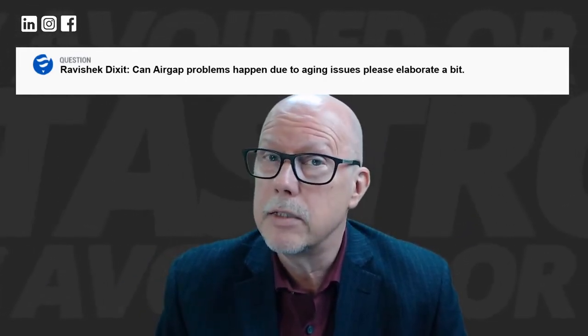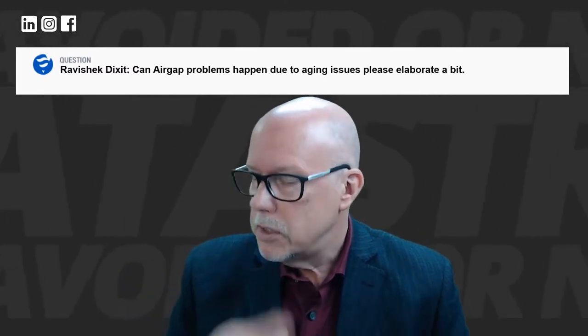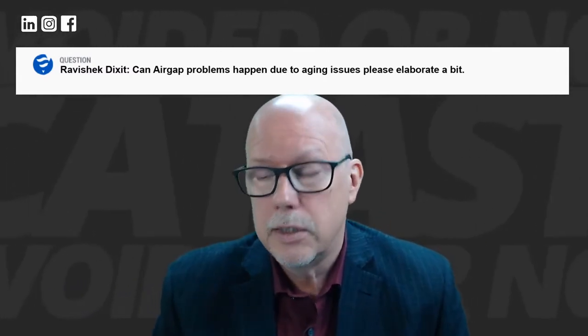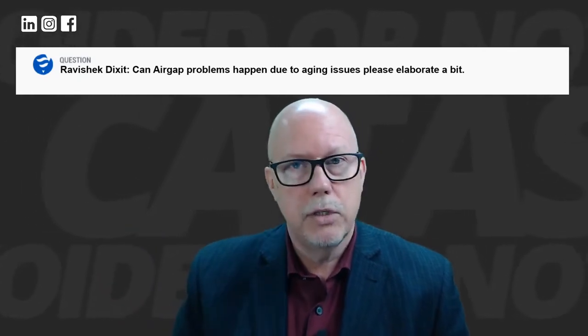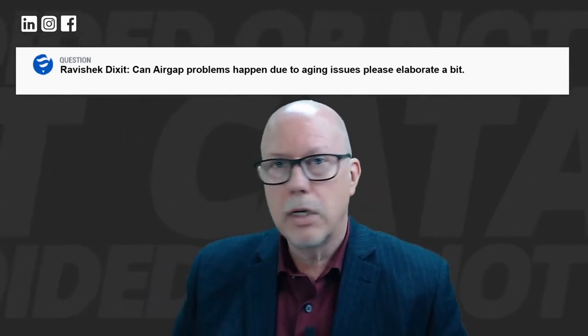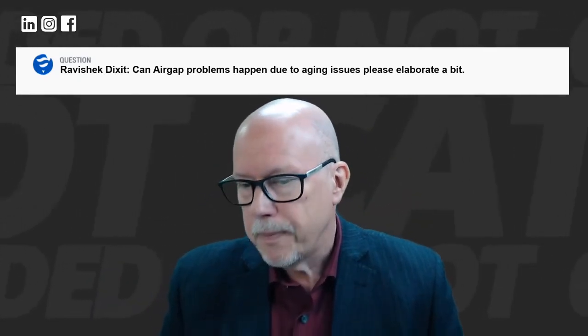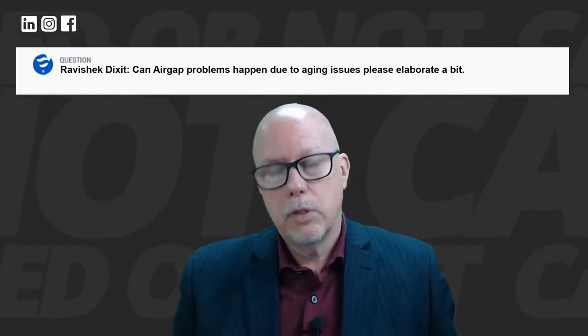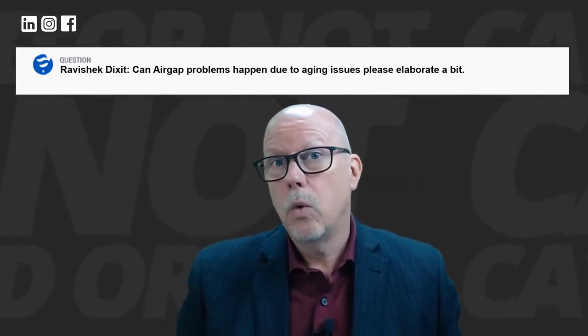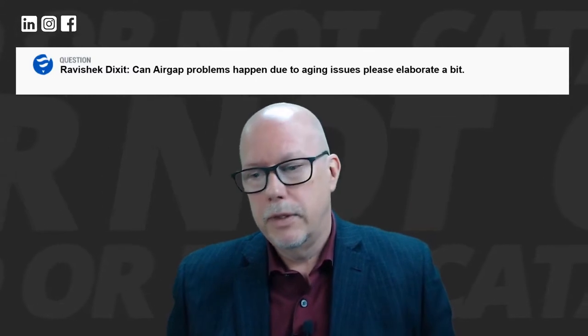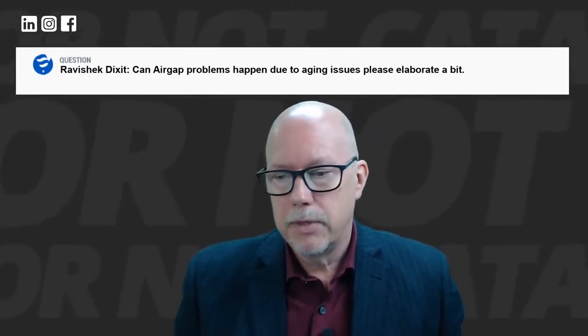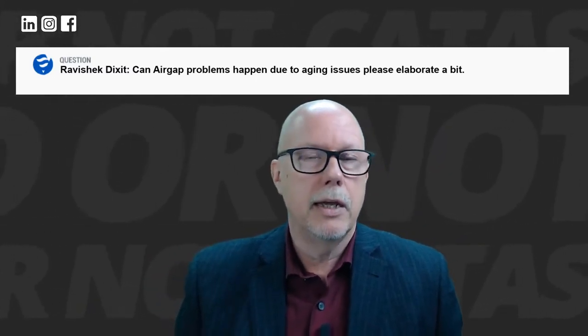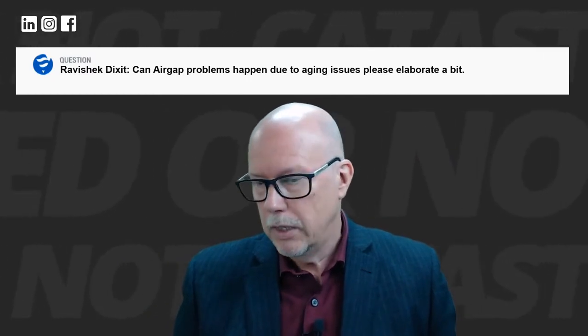So our guess was that they could run this unit safely, since it had been running like this for 20 years. The utility put the machine back online, and it's been running for three years now, fine. So sometimes the results look horrible, but if the unit is very old and there's been no damage, nothing observed evolving, you can get away with those results.